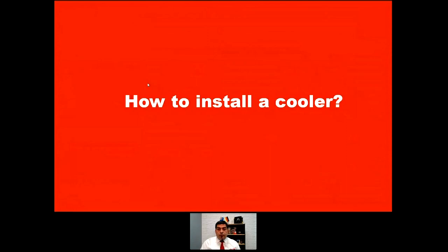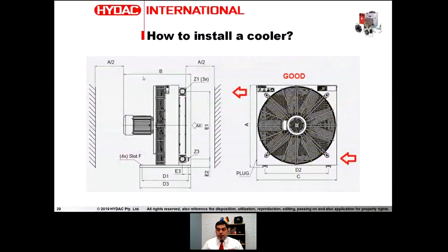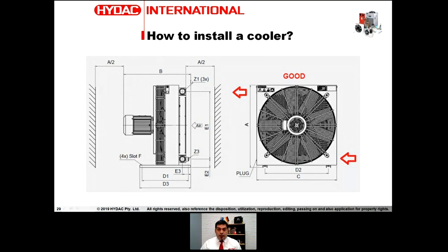How to install a cooler — something people still get wrong every day. There are two aspects: the air side and the fluid side. On the air side, at the end of every catalog for the selected series — in this case the ACLN — there is a value called A2. This tabulated value is the required distance between the back of your electric motor and a wall or any constraint. The same applies at the front. Always read the manual and ensure your installation is within this envelope: more than declared is fine, less can cause problems.